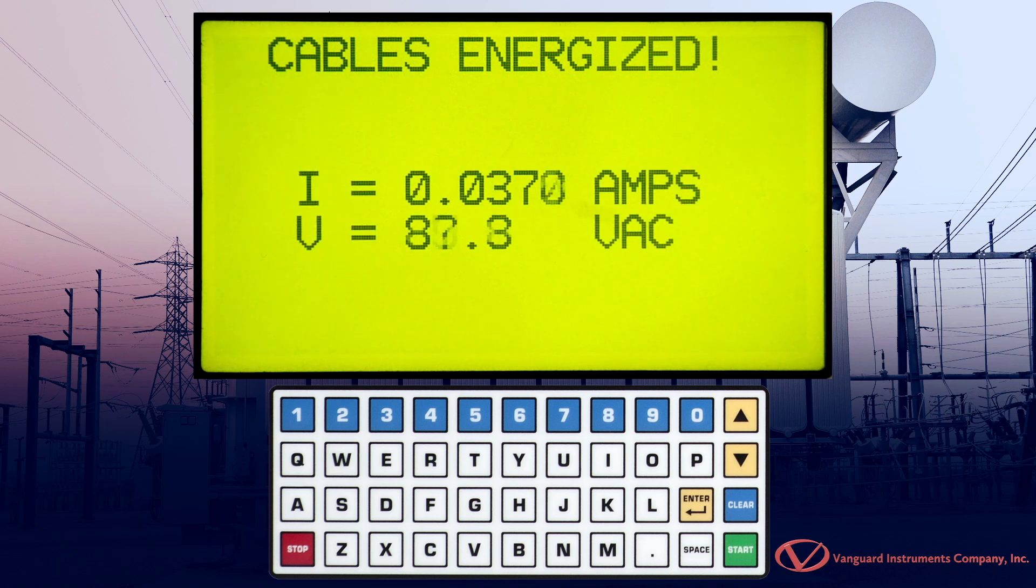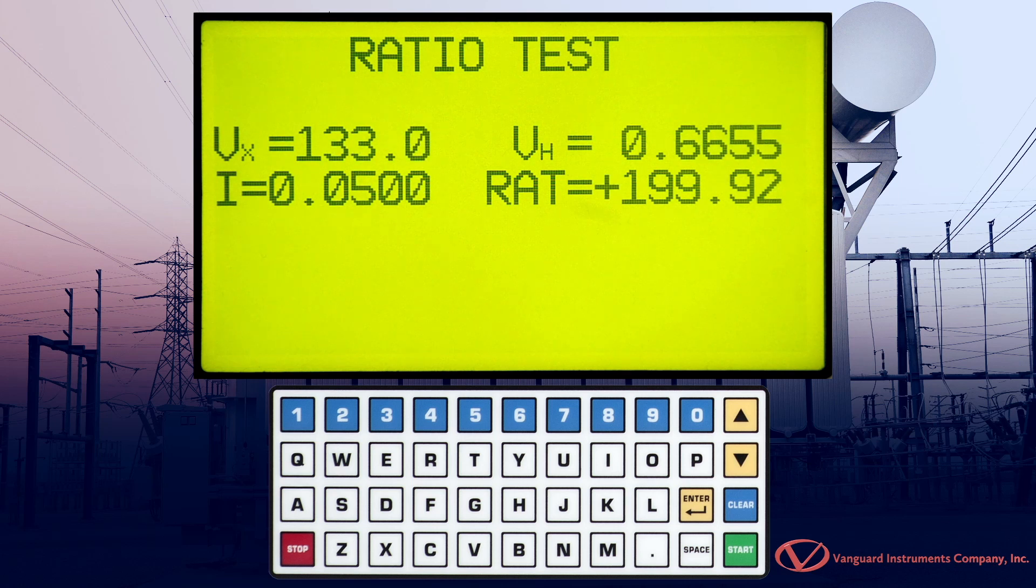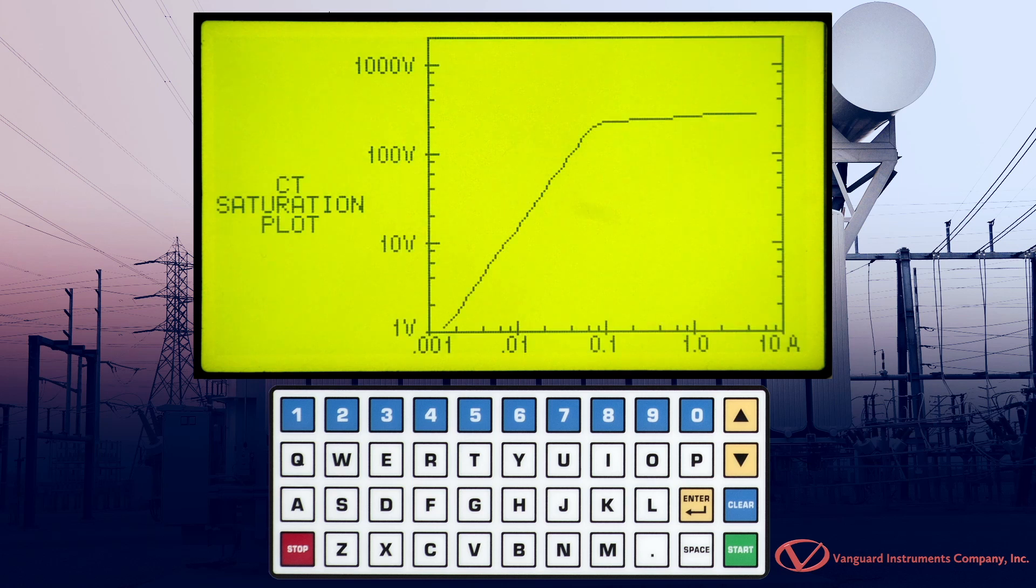Next, the ratio test will be performed. The voltage will be ramped up to the selected test voltage and then ramped down. When the testing is finished, the CT saturation curve will be displayed.